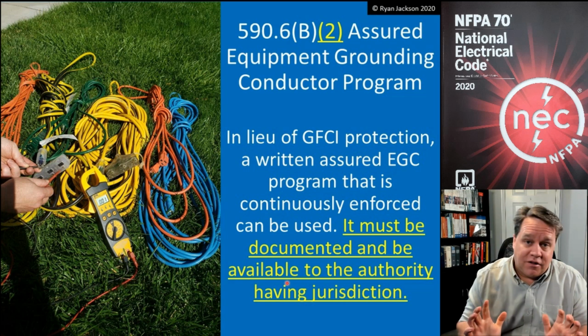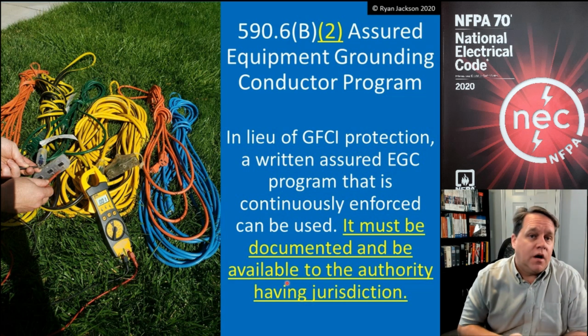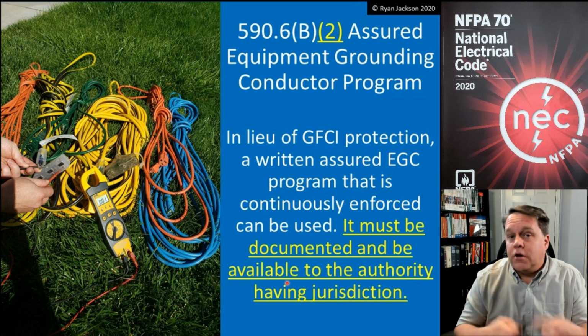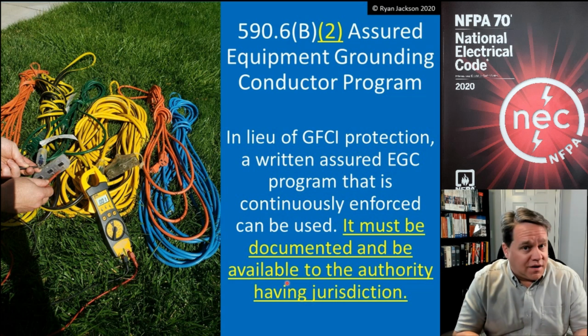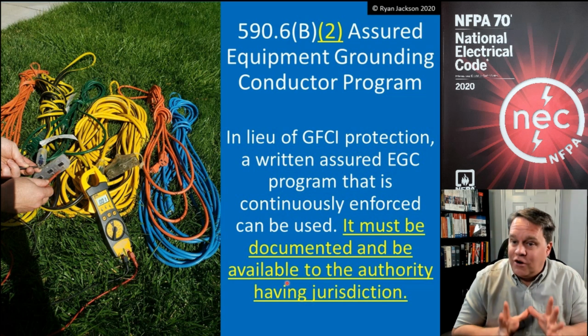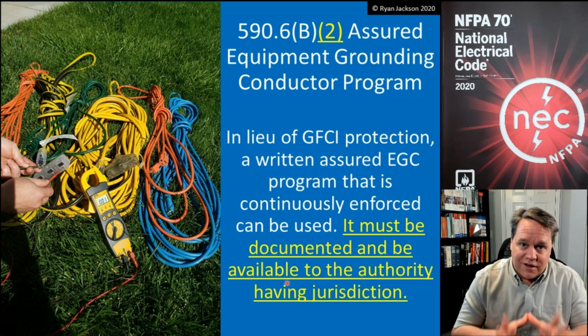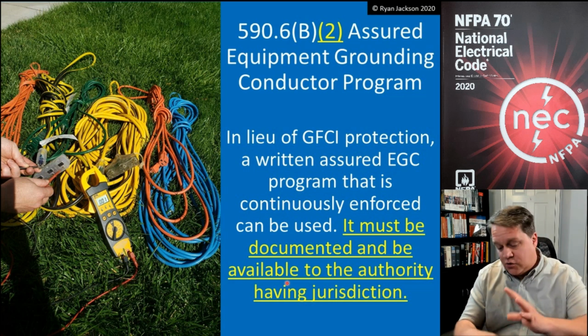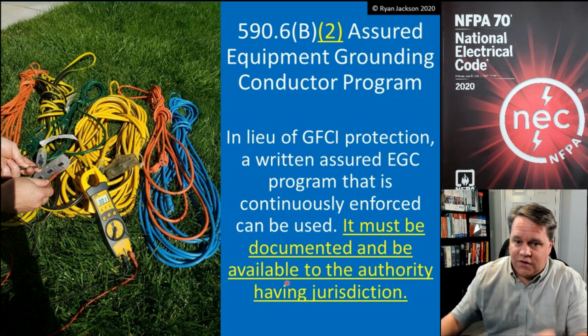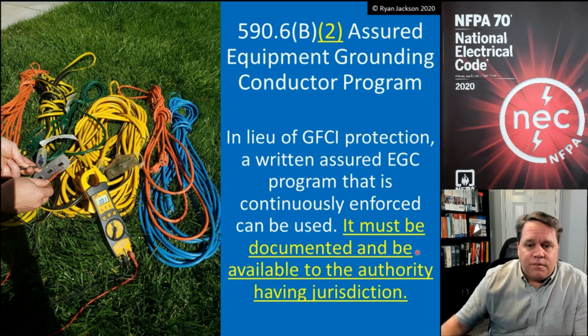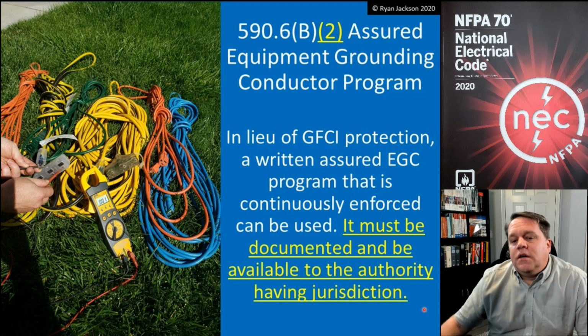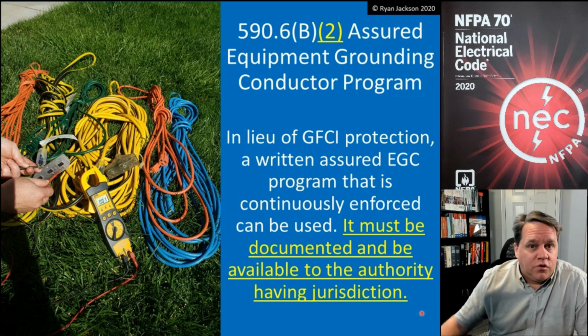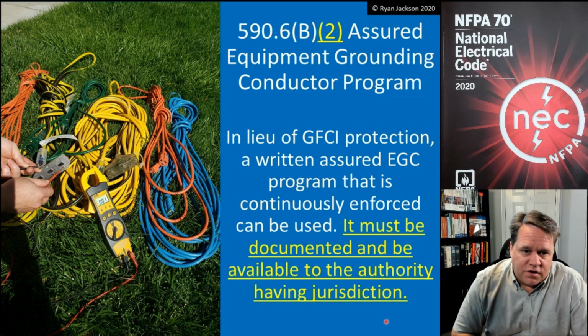So again, I'm not telling you what to do. You want to use the Assured Equipment Grounding Conductor Program, go ahead. The code recognizes it, OSHA recognizes it, but please make sure you do it right. Look at OSHA 1910 and 1926 and make sure you're following everything correctly. So, in lieu of GFCI protection, a written Assured Equipment Grounding Conductor Program that is continuously enforced could be used and has to be documented and be available to the authority having jurisdiction.